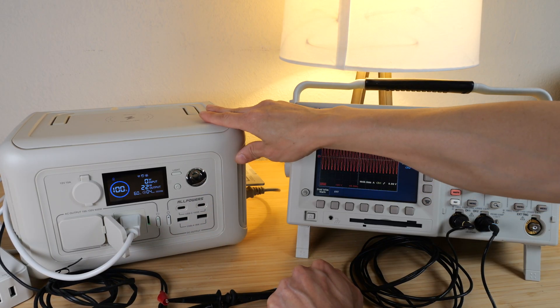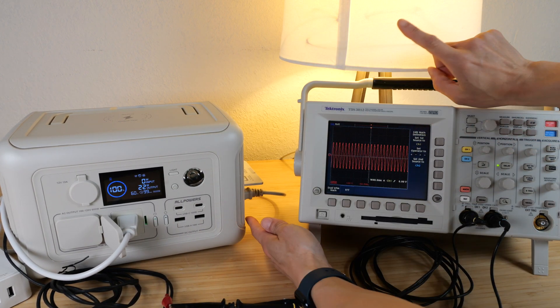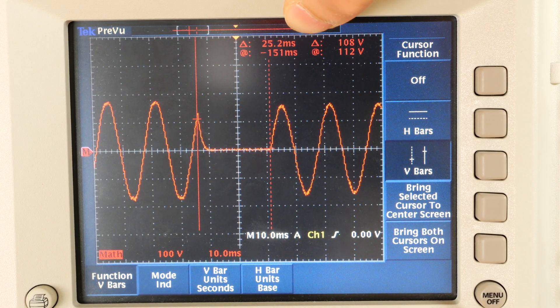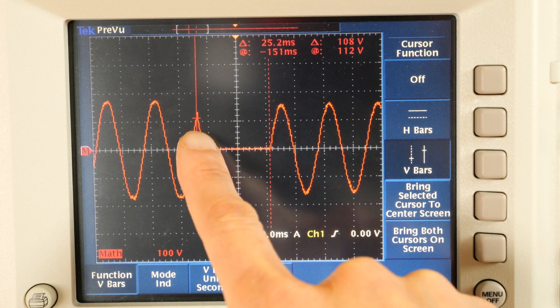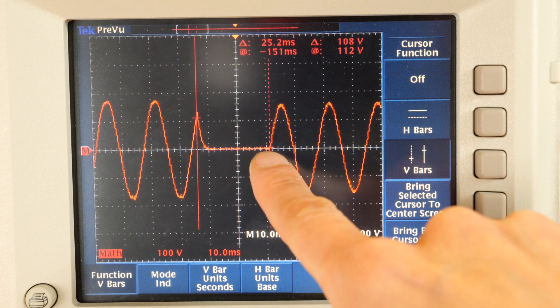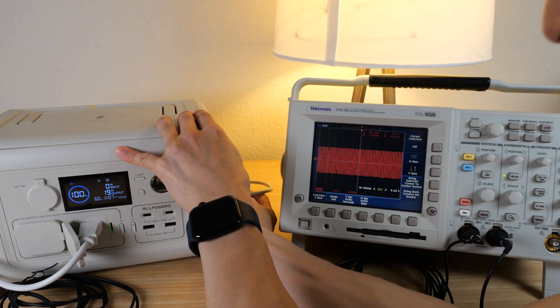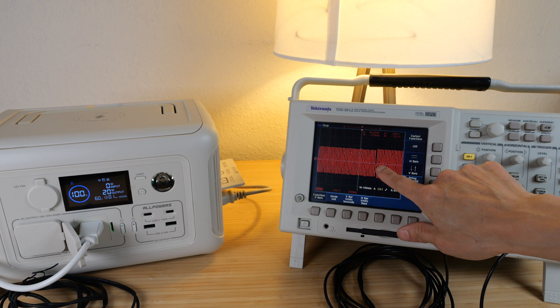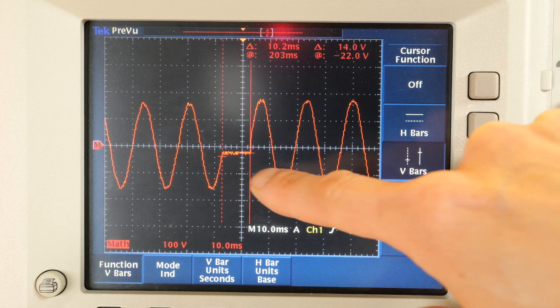The lamp is connected to the AC output being used as a UPS while plugged into the wall. When I pull the plug, watch the lamp flicker slightly. I'm measuring a switchover time of about 25 milliseconds — not exactly the 10 milliseconds shown in the manual. Right when it cuts off, voltage drops to zero almost immediately, showing very little output capacitance. Then 25 milliseconds later the battery inverter kicks in and AC output resumes. When plugging back in, it takes a few seconds — about 3 seconds — to reconnect to AC. On reconnection, it takes about 10 milliseconds before it reconnects to grid power.